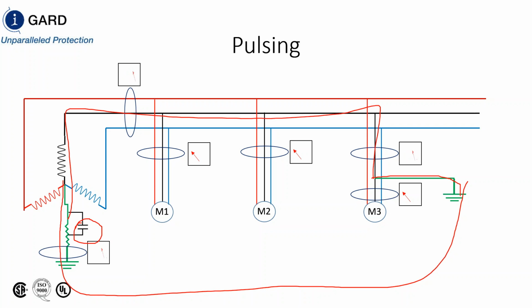So now our fault current, you can see that the pulsing only exists in the faulted path. The unfaulted feeders, you're looking at three-phase current, zero sequence current, which is going to be zero. It's always going to be zero. Once you pass the point of the fault, it's going to be zero. Only in the fault, once you pass the fault here, you're measuring zero.